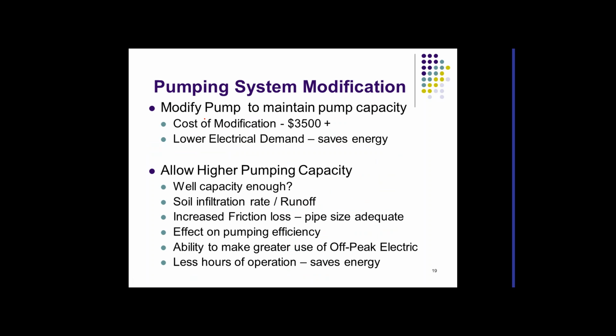So one of the issues is whether to modify the pump or not. If I modify the pump, the biggest deterrent is it costs money. But if I do it, it lowers my demand rate, so I'd get that 17 kilowatt savings of energy. Now, the one thing nice about a motor is I don't necessarily have to put a different motor in. If I reduce my demand, the amount of energy that the motor requires to run will also reduce. Although if it's below 50% of load, it may reduce the efficiency of that motor, so it may not be as efficient operating, but it generally will save energy by doing that.